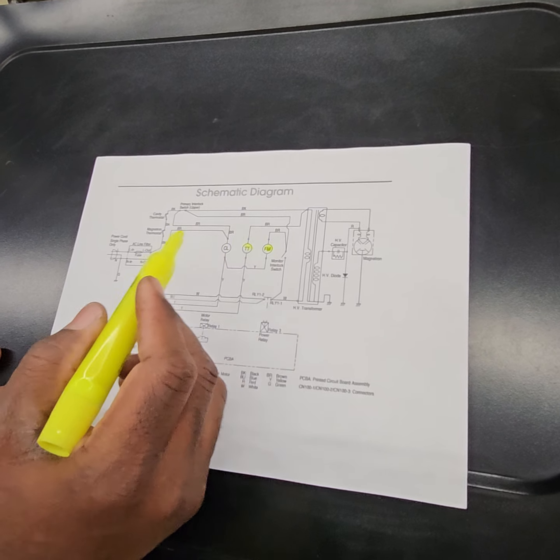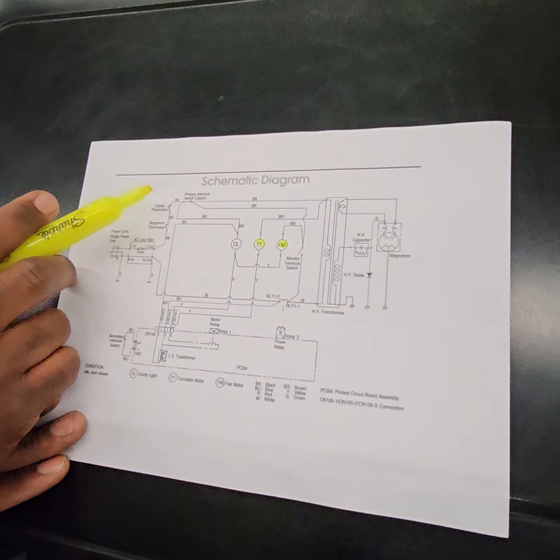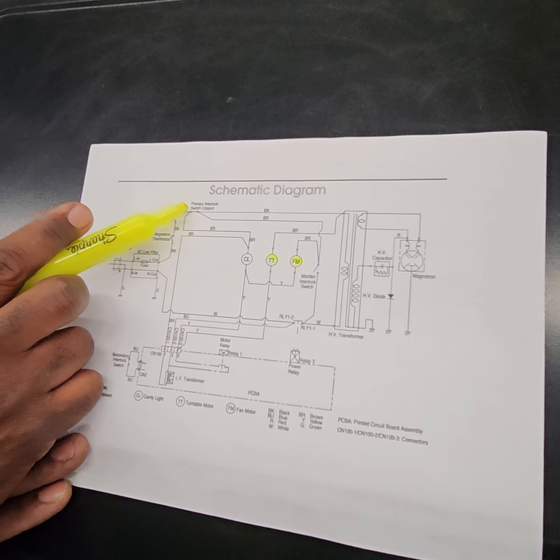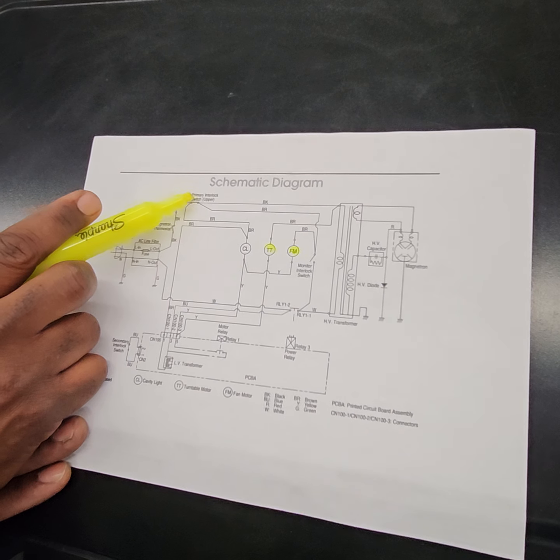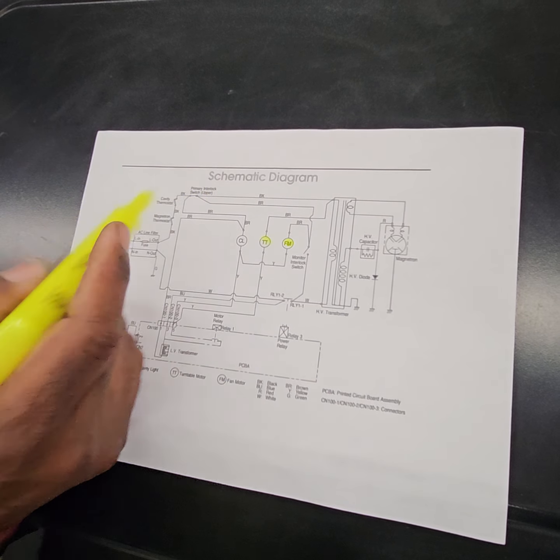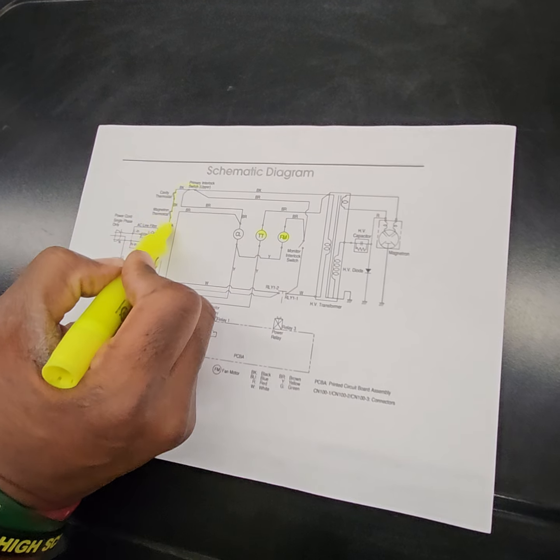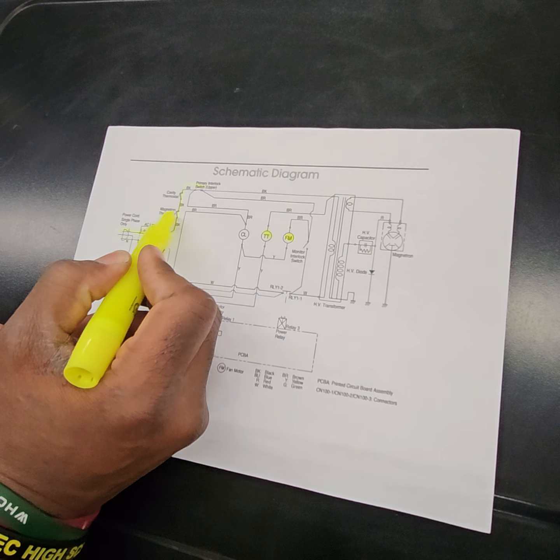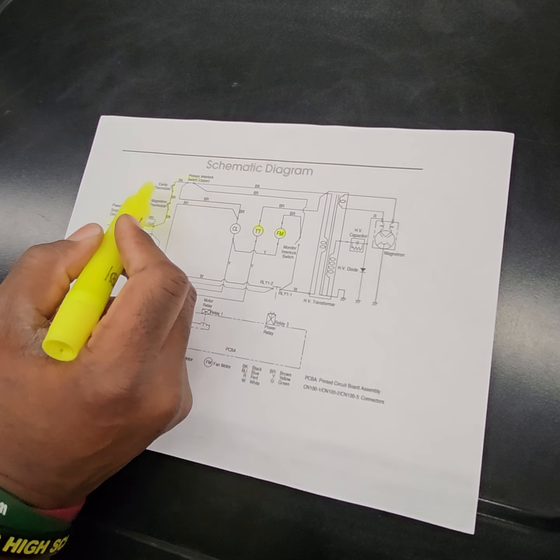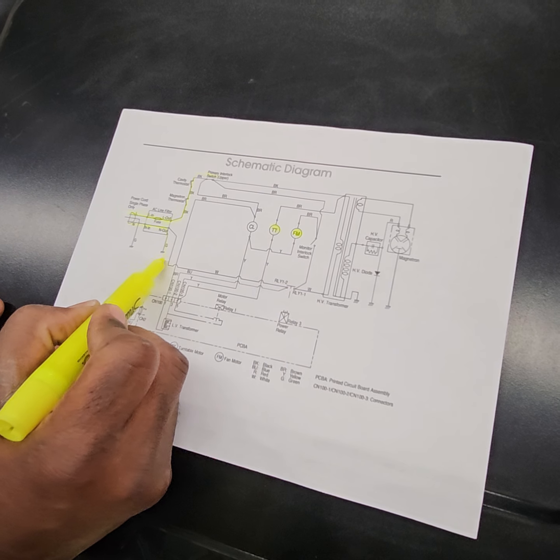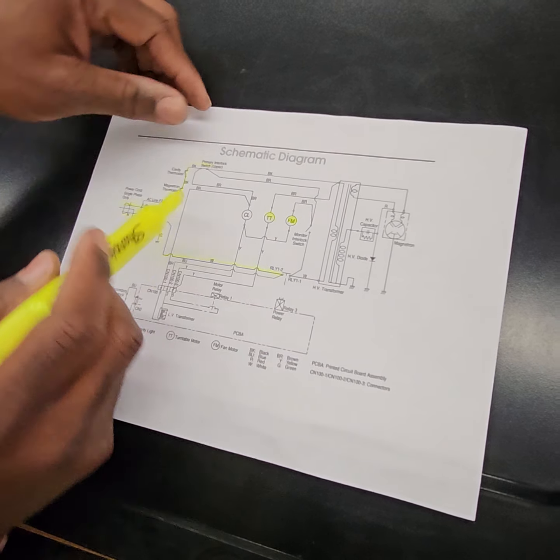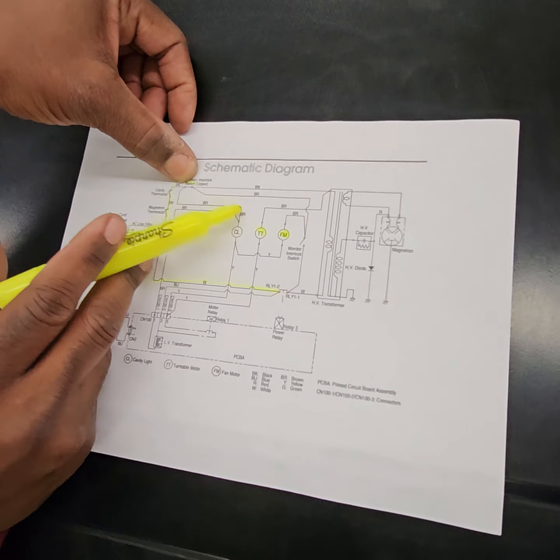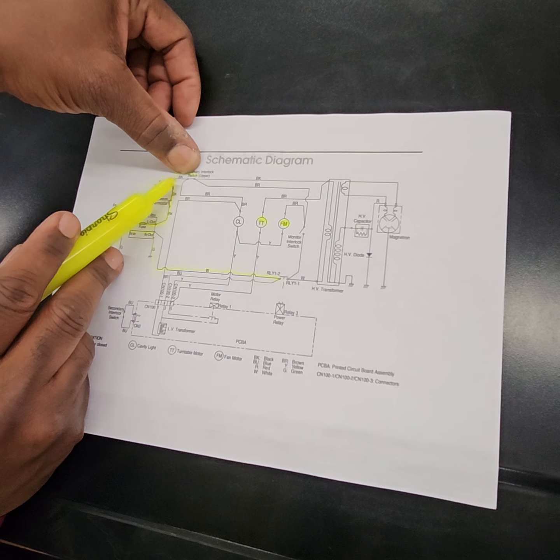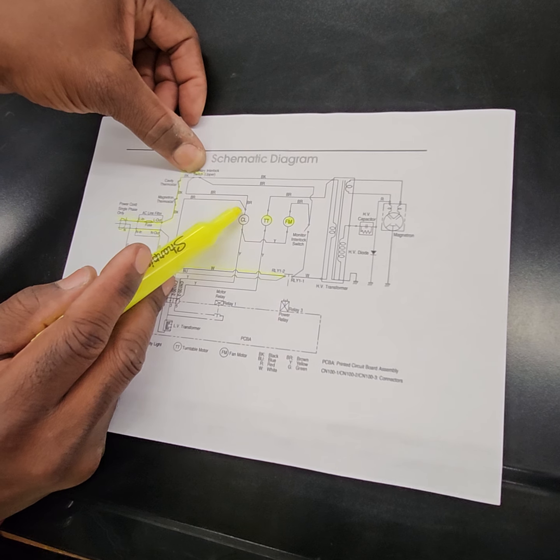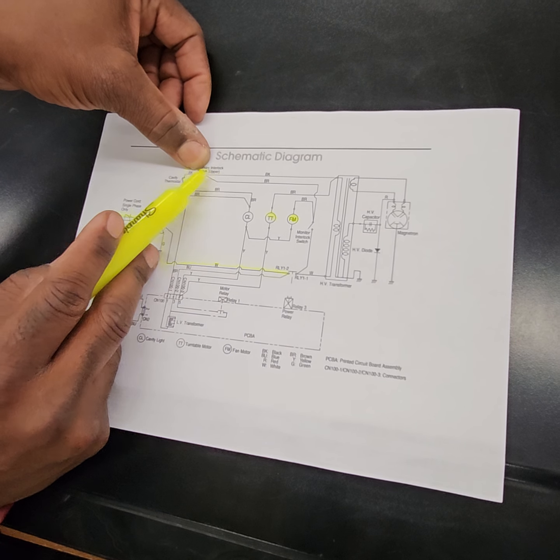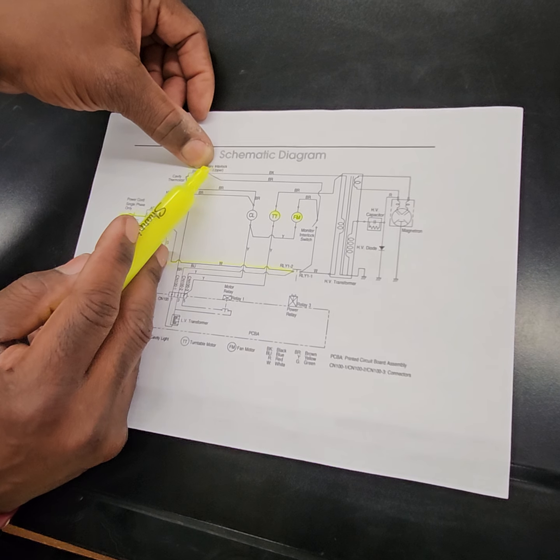Okay, so at this point, we're gonna look at the circuit. Based on this, if the primary interlock switch is open, this circuit does not work. So that's probably where I'm gonna start first. We're gonna ignore the filter, the magnetron thermostat, the cavity thermostat, and also the relay, because, like I said, if this switch is open, none of these work. As you can see, the clock gets its path from here, so that will work. Everything after this section is not working. So we're gonna go to the primary interlock first.